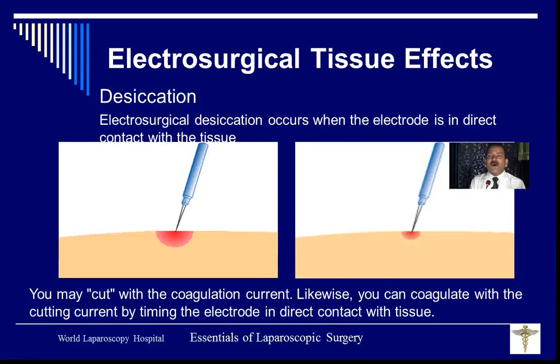Now one more problem of the bipolar. First problem of bipolar, it doesn't cut. Second problem of bipolar, every instrument cannot be bipolar. Third problem of the bipolar, for the same wattage of the current, the lateral spread of the heat may be a little more unless you keep the wattage less. Fourth problem of the bipolar, it doesn't fulgurate also. It only desiccates.